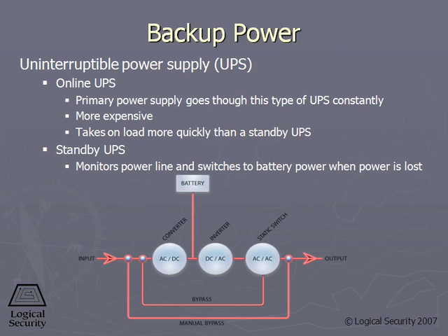These are typically a little more expensive, and you wind up replacing those batteries a little more often because they have this continuous flow of power through them that actually continuously charges those batteries. But again, those batteries tend to wear out a little more rapidly. The alternate type of UPS is the standby UPS. Now, this is where the main power supply from the AC power source to the device is consistent and direct. However, we trickle charge the battery that runs in parallel to this AC power feed. Now, the problem with this is, if the power goes away, there is a momentary switchover process.